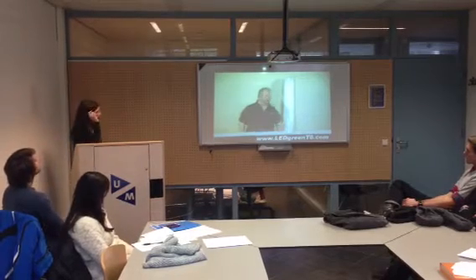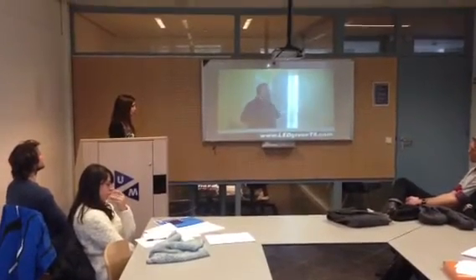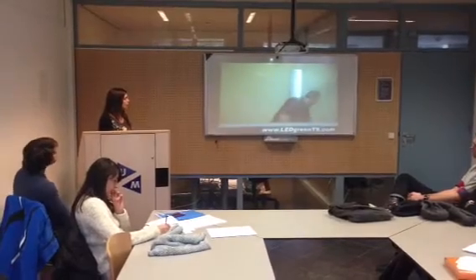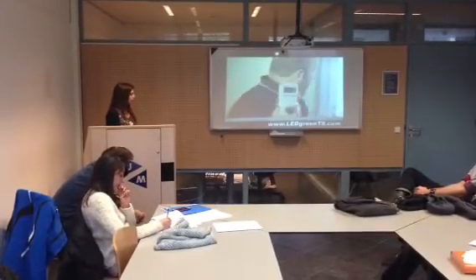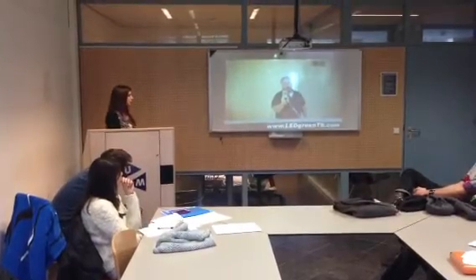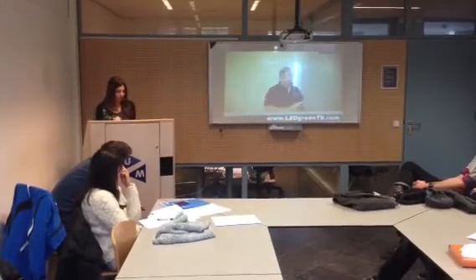That is a direct replacement for standard fluorescents. What I have here is a light fixture with a T8 fluorescent tube in it that's run with the ballast. Next to it is an LED light that is line voltage. It does not require a ballast, but it gives out a similar amount of luminance quality. The big difference between the two is the amount of electricity they use. If I turn off the LEDs, you can see that the fluorescent tube is actually burning between 38 and 39 watts of power. In comparison, the LED tube is now burning about 8 to 9 watts of power for about the same amount of light. So we're looking at about a 70% energy savings for not much more time than it takes to change out a light bulb. So if schools and hospitals and government buildings are really interested in saving energy and making a difference, this is the simplest and fastest way of making that happen.